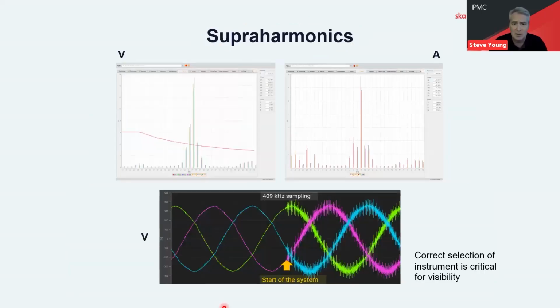So this is an example. The black chart at the bottom, the voltage one, is a chart showing, if you like, the sinusoidal waveform before the system started on the left-hand side of the image, and then after the PV, the photovoltaic inverter, was switched on. You can see the feathering on the waveform that's only visible if you're using quite an advanced type of power quality instrument. So this is above harmonic, normal harmonic range.